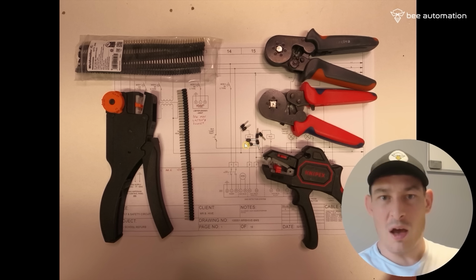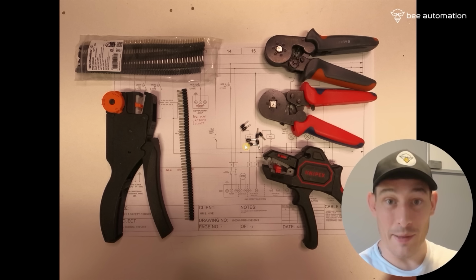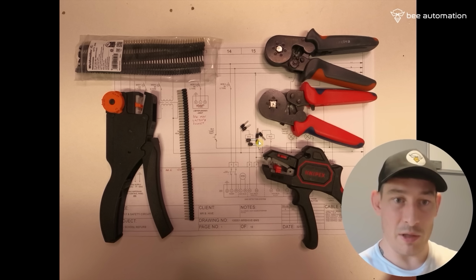Only using 1.5mm cable for 99% of cables in this panel, so 1.5 single ferrules, also using some double ferrules.